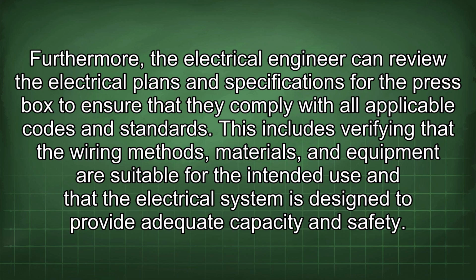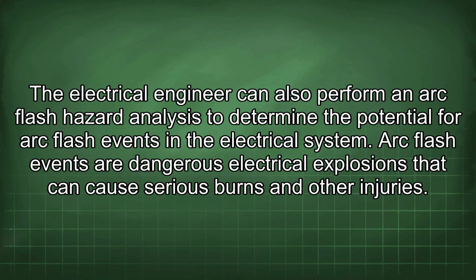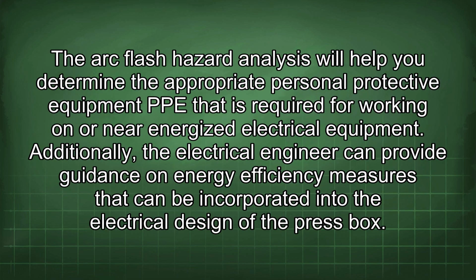This includes verifying that the wiring methods, materials, and equipment are suitable for the intended use and that the electrical system is designed to provide adequate capacity and safety. The electrical engineer can also perform an arc flash hazard analysis to determine the potential for arc flash events in the electrical system. Arc flash events are dangerous electrical explosions that can cause serious burns and other injuries. The arc flash hazard analysis will help you determine the appropriate personal protective equipment (PPE) that is required for working on or near energized electrical equipment.